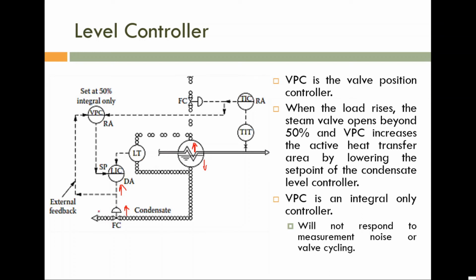So how to open this control valve? To open this control valve, we can decrease the liquid level. We can decrease the liquid level only after this control action. So before that, we need to decrease this liquid level. So what can we do? We can change this set point. In order to increase the control signal, we decrease the set point. Means we want less liquid level inside this one. So for the time being, this set point is small, measurement is small. So the LIC will give a large control signal. Okay, so this valve is open.